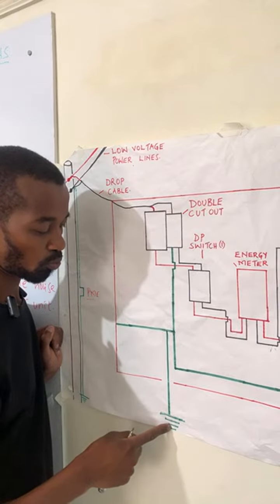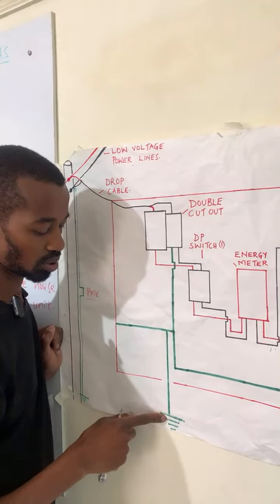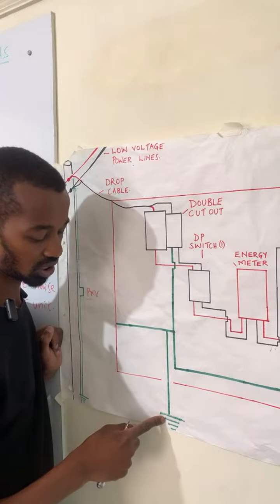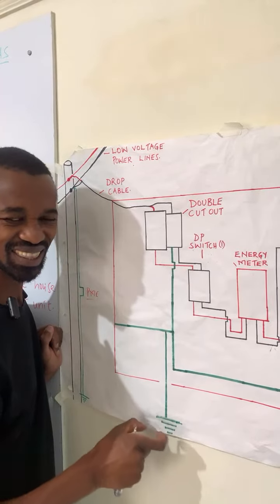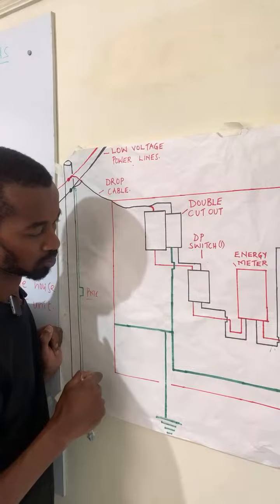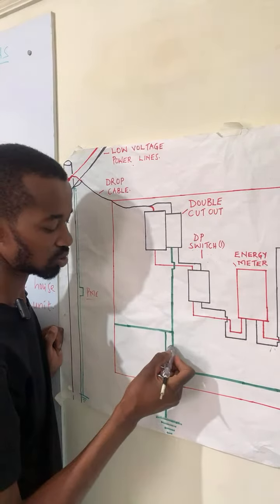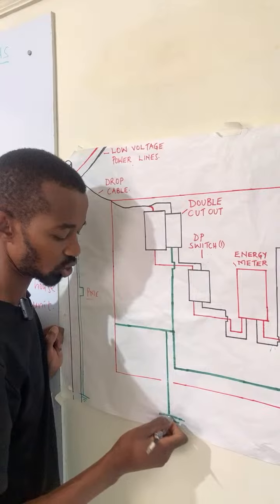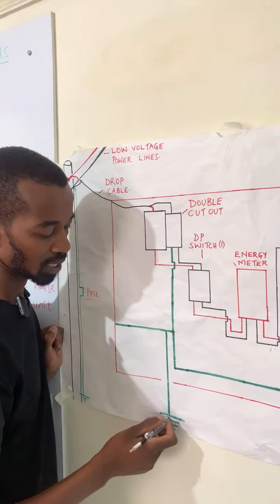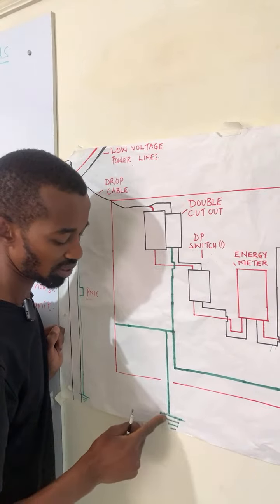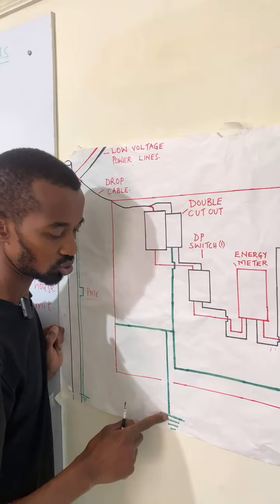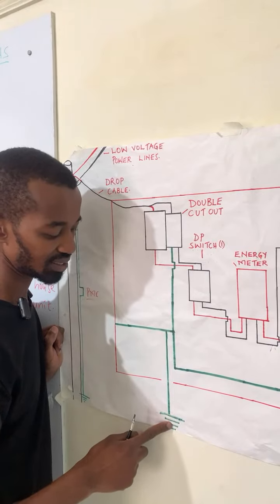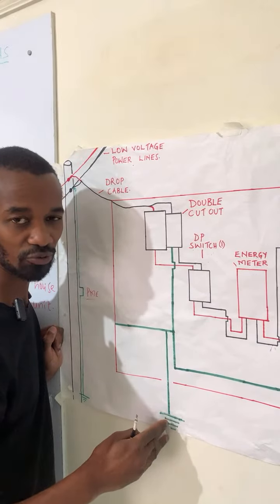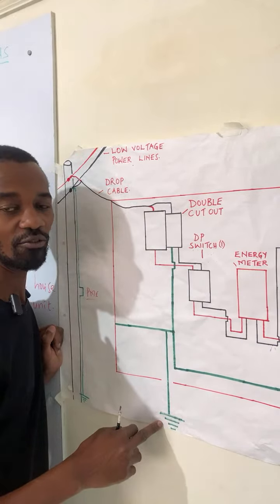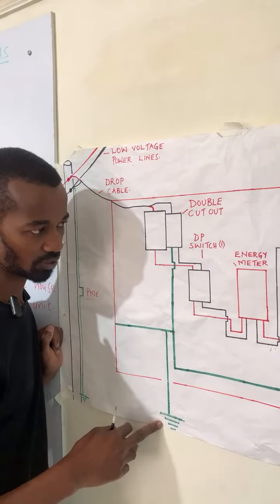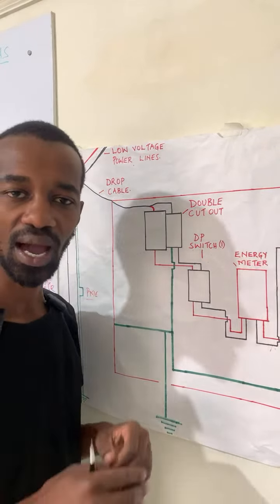So when doing the electrical installation, you must ensure as an electrical technician that the earthing that is done there is perfect. So let's say, for instance, you are doing the earth rod connection just underneath the meter box. You must ensure that the earth rod is in a conducive environment, in the sense that the excessive charges will be able to find their way to the ground very fast and very safely. That is how we define earthing.